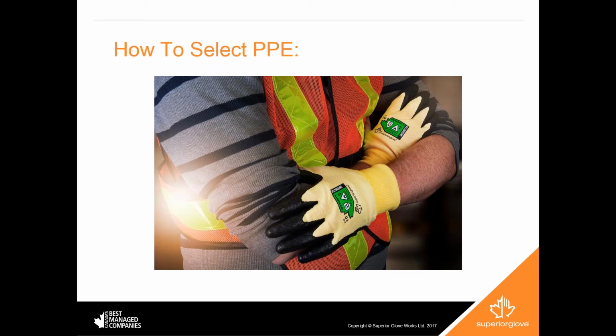So when you're choosing your arc rated gloves, some of the things you need to look at are the arc thermal performance value, or what everybody generally refers to just as the ATPV. This is the incident energy needed to cause a second-degree burn. It might sound a little confusing, but if you wanted to think about what is 1 cal, think about taking your finger and sticking it to the top end of a Bic lighter that's lit and leaving it there for 1 second. That's a very generic example of what 1 cal would be like.